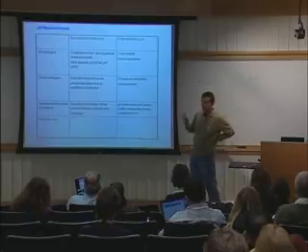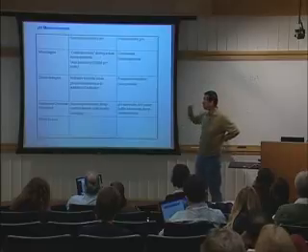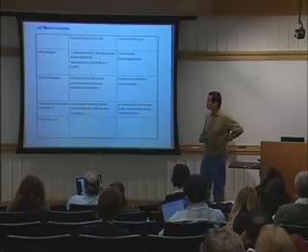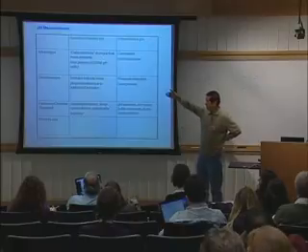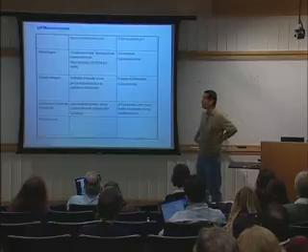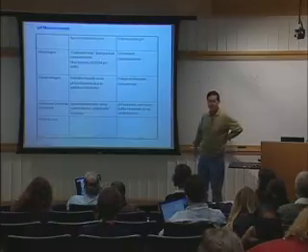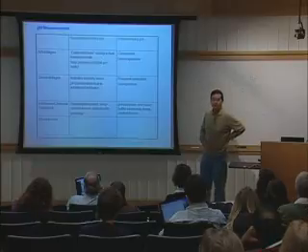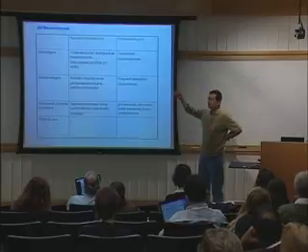And that uncertainty is quite large, 0.01 pH unit, which is not acceptable for spectrophotometric pH measurement, because we talk about the precision of this on the level of the fourth decimal place. And easily you can get to the third decimal place if you do everything as Andrew and Chris demonstrated. So this is a work in progress.